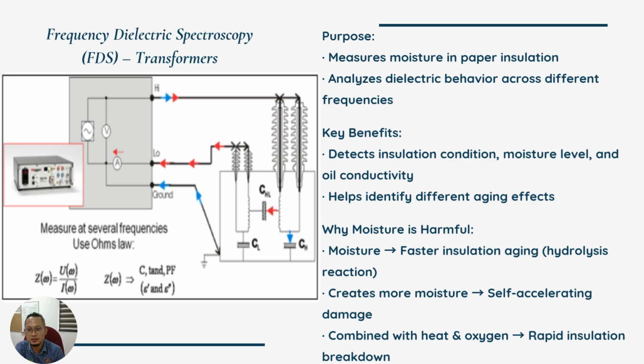Frequency dielectric spectroscopy, or FDS, is another valuable tool for assessing transformer health. FDS measures the moisture in the transformer's paper insulation and analyzes its dielectric behavior across different frequencies. This test helps detect insulation conditions and moisture level, which are vital for assessing the aging process of the insulation. Moisture, when combined with heat and oxygen, accelerates the breakdown of insulation, making tests crucial for early detection of degradation.